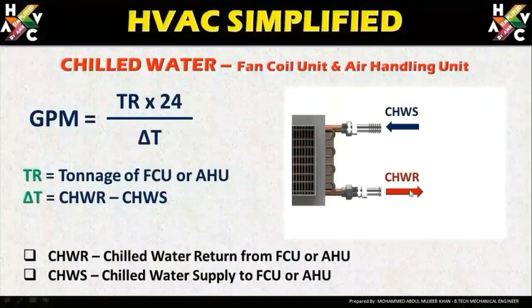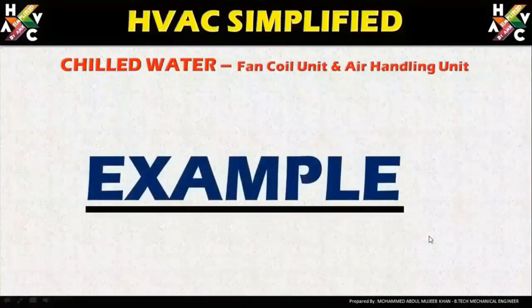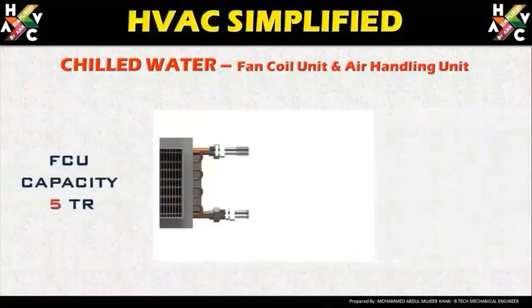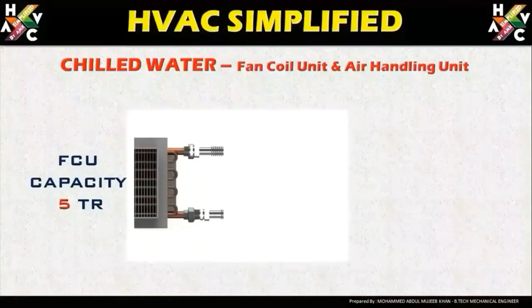Now let us analyze with an example to find out how we can derive a GPM for any fan coil unit. We are going to look into an example from which I will explain how we can derive the capacity of a 5-ton fan coil unit. Let us say the capacity of the fan coil unit is 5 TR.